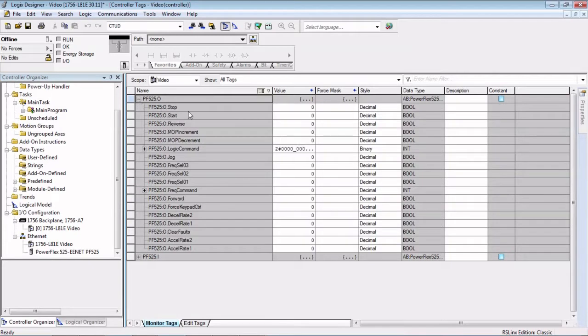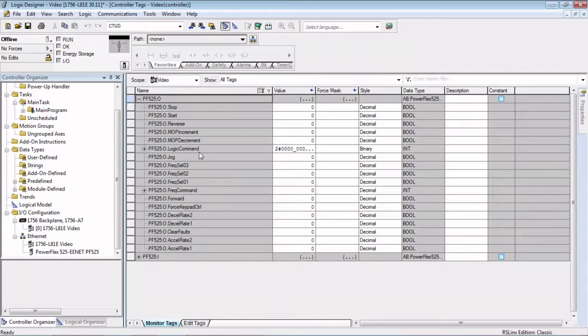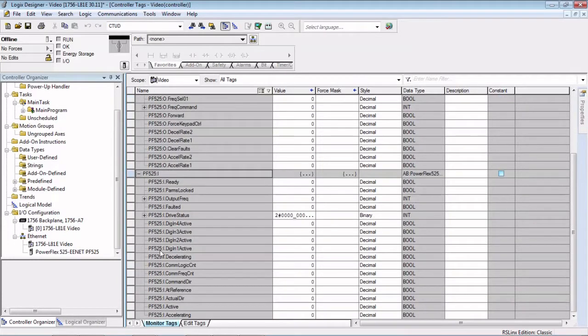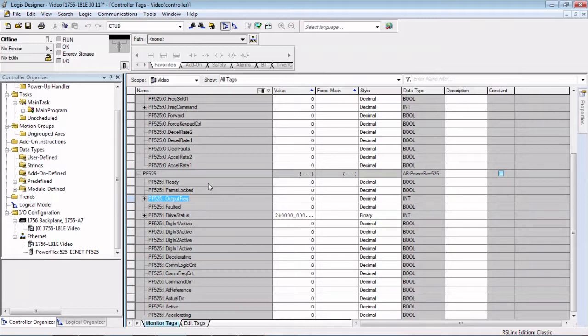You can see stop, start, reverse, jog, increment, decrement. All these tags were made for you, so you don't have to write a message block of a random integer and then move those bits in that integer into tags that make sense. The tags have already been created for you that make sense. And then we also have our indication, our status word coming back as well as the output frequency.